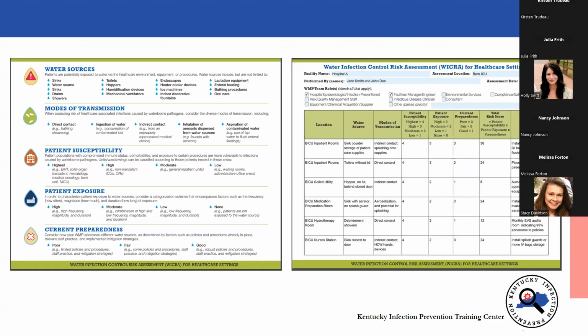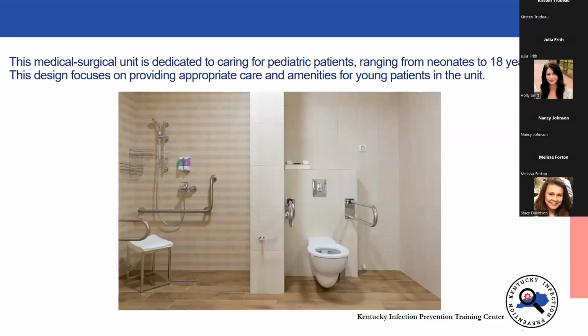Preparedness, we don't entirely know, but we do know that there's not splash guards. So if we look at practice across time, it seems pretty likely that people are going to encroach onto the sink. What is the process for making sure that the aerator, if it exists, is changed out on a regular basis? And so maybe the preparedness is super good and they've got a great plan, or maybe it's not, and we need to really look and see what our opportunities are that could exist.